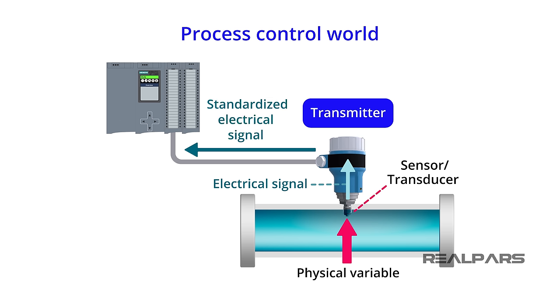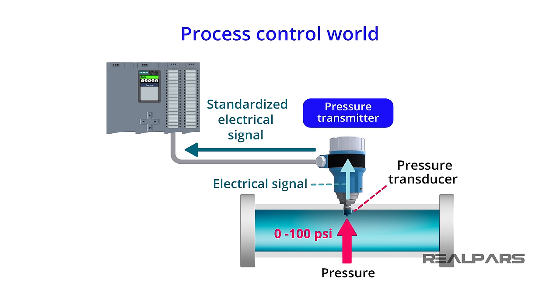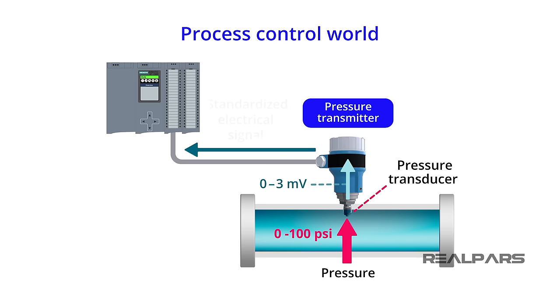Here's an example. We're measuring a Process Pressure with a range of 0 to 100 psi. Our Sensor Transducer performs the initial measurement and converts it to an electrical signal of 0 to 3 millivolts. The Transmitter then converts that signal to a standard signal of 1 to 5 volts, which is received by a PLC analog input module.